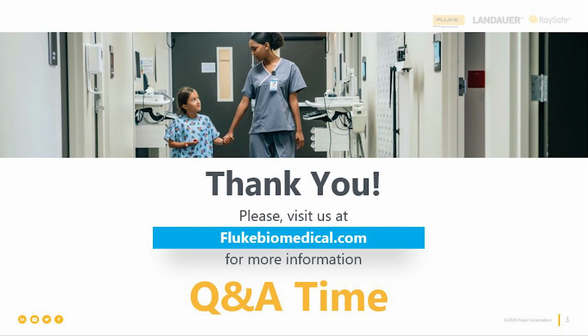Or you can customize that. You can pick and choose from those standards-based tests, and when you select them, they become your onboard workflow, and they come with the assessment against the standards. And then of course the general test, where whatever you connect to the INCU2 is what's going to be measured over the same time base. So you can see what changes over certain periods of time and different conditions within the incubator or on the radiant warmer table.